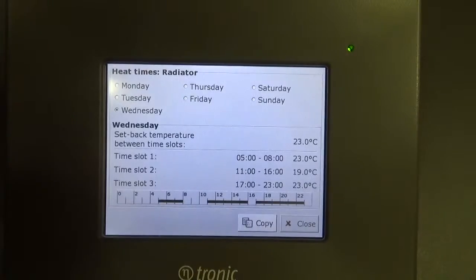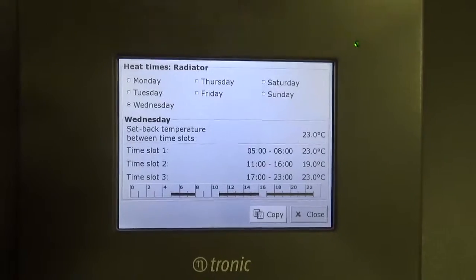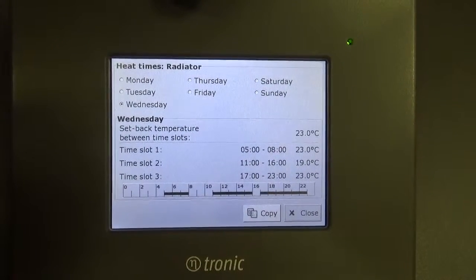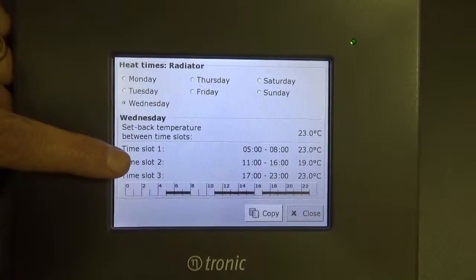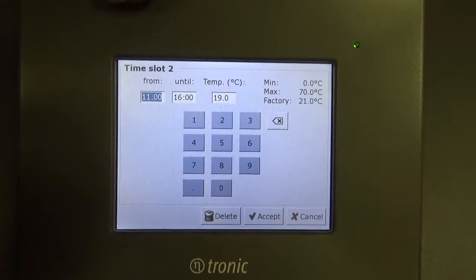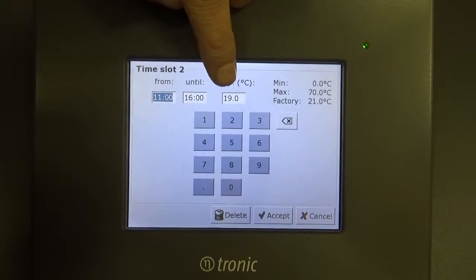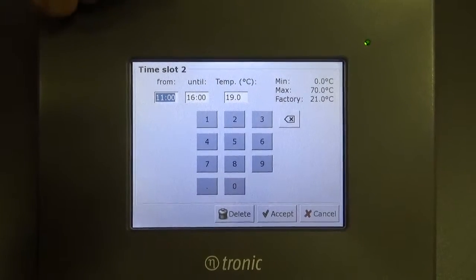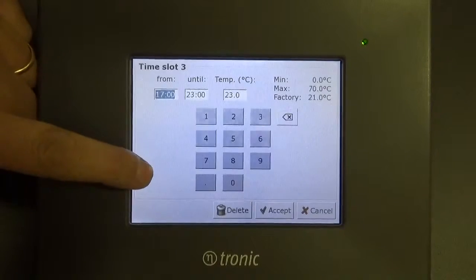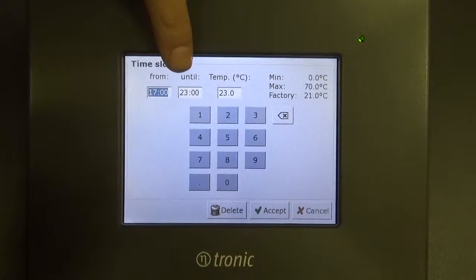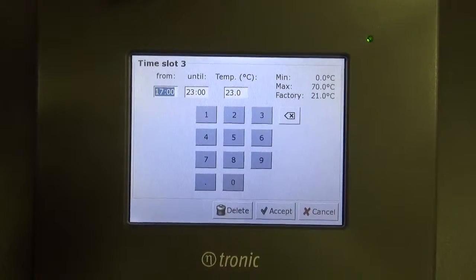Then I can accept that. So now we've changed time slot one to start at five o'clock in the morning, finish at eight o'clock, and go to 23 degrees. If we click on time slot two we can change the settings on that — at the moment it's set back to 19 degrees between eleven o'clock in the morning and four o'clock in the afternoon. We can accept that. The third time slot is from five o'clock in the afternoon to eleven o'clock at night, and again the temperature is going to be 23 degrees.